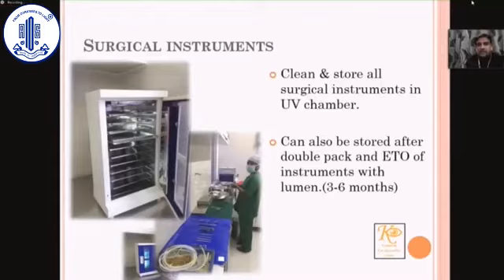The most important is the surgical instrument maintenance. The main aim of storing a surgical instrument is to ensure that they are clean and free of moisture before storing, and also ensure that moisture doesn't build up during storage. All instruments have to be cleaned as usual by following the 3-bin technique, dried properly with either a high flow air gun or kept under proper aeration. They are then packed under the trays. These trays are then placed inside a UV chamber until they are to be used again. If you do not have a UV chamber, they can be kept open in a well aerated environment. Alternatively, you can also pack these instruments under ETO, double pack them, and they can be stored for a maximum of 6 months or until you use them.